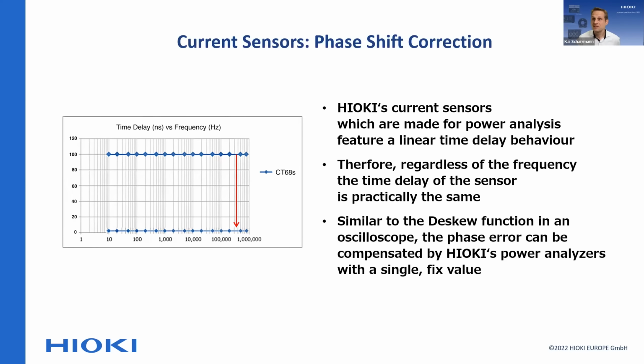And why is it so important for Hioki to have this time delay in a very constant way? And what is actually the time delay? I always use the example of an oscilloscope with 2 channels. If you want to match the signals coming into the 2 channels, you have a deskew function, because you might have latencies in a sensor, and that's exactly what we're talking about. There is a latency in the sensor. In our case, it's a constant latency, which is frequency independent. And then you have the deskew function in that oscilloscope, and that allows you to bring those things together.